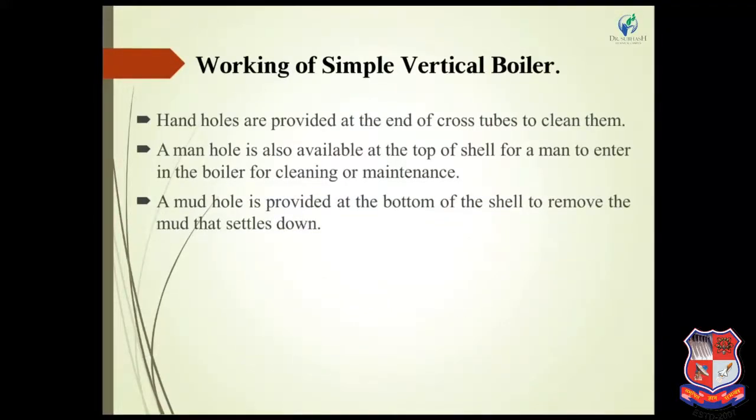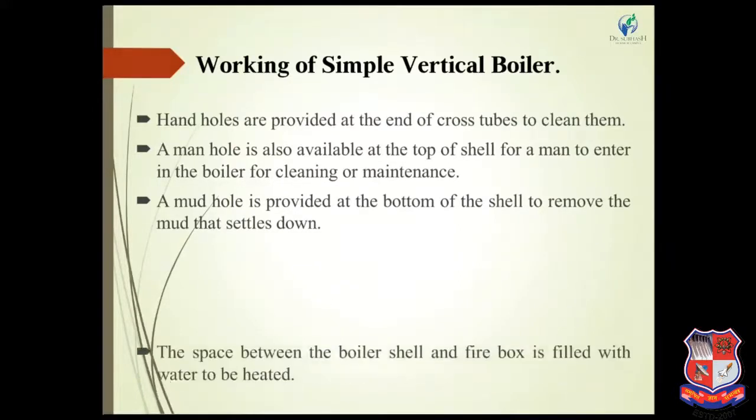A mud hole is provided at the bottom of the shell to remove the mud that has settled down. Due to the high amount of coal collected in the grate, many types of ash, sometimes in a moisture condition, jam the bottom of the boiler and choke up the firebox. At that time the mud hole is required for cleaning or removing the settled material from the ignition chamber.